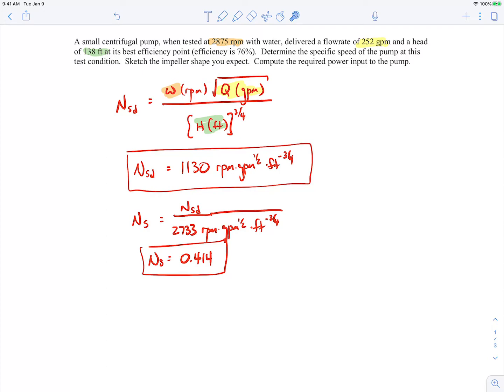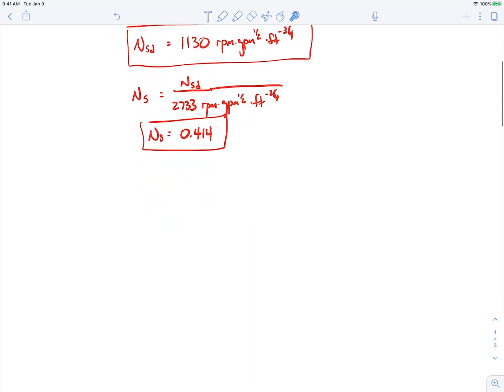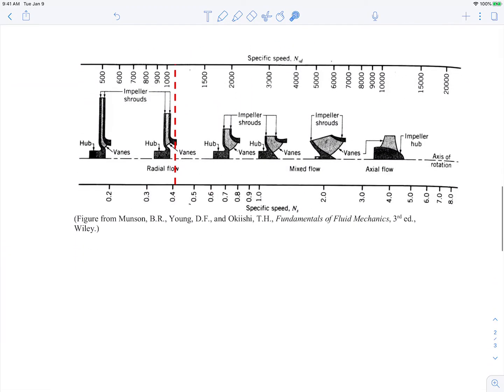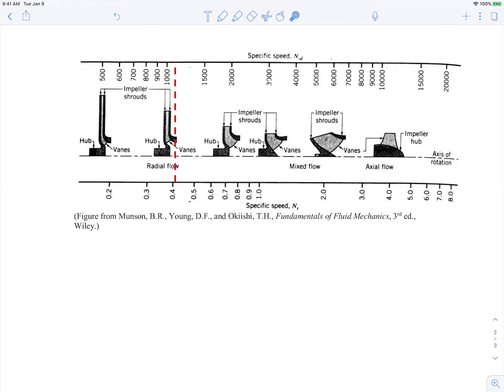What we do with that dimensionless specific speed is it'll tell us what general class of impellers or pumps will be most efficient for our particular application. If we go to a plot, just remember these numbers: 1130 and 0.414. We can go to a plot showing the type of pump impellers that are most efficient for a given specific speed. You'll see up here, this is the dimensional specific speed. We were at 1130, so right there. And this is the dimensionless specific speed. We calculated 0.414, which is right there. You can see the most efficient type of pump impeller for our given application is a radial flow impeller.